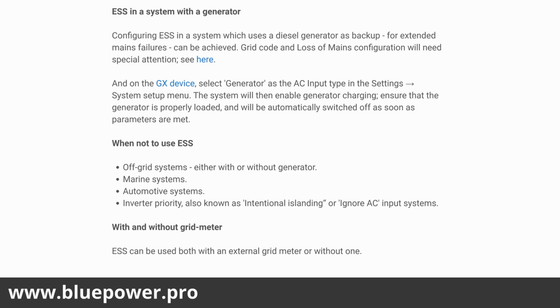So when not to use ESS, that's in off-grid systems, and marine systems, automotive systems, and inverter priority, as in dedicated ignore AC or intentional islanding, where you want to intentionally disconnect from the grid at times.